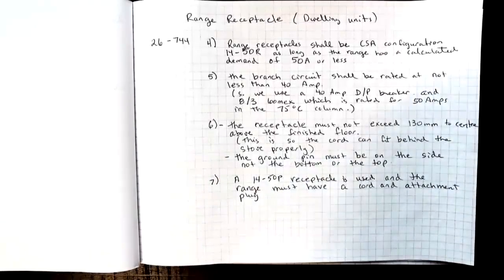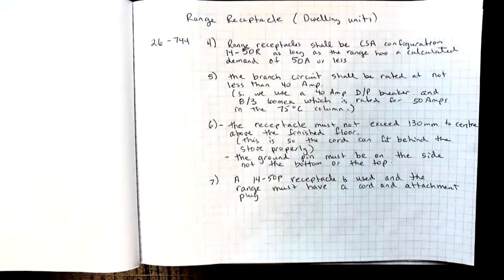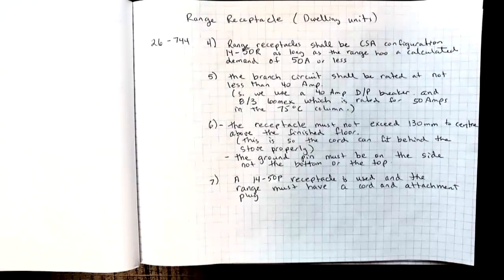Let's look at the CEC rules for a range receptacle within a dwelling unit, 26-744. Sub-row 4 says range receptacles shall be CSA configuration 14-50R as long as the range has a calculated demand of 50 amps or less.